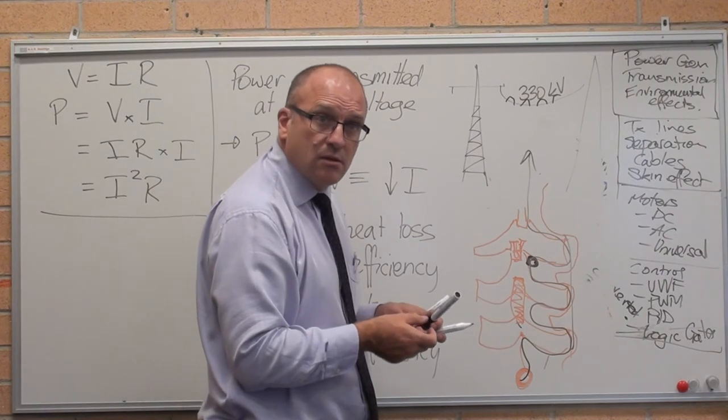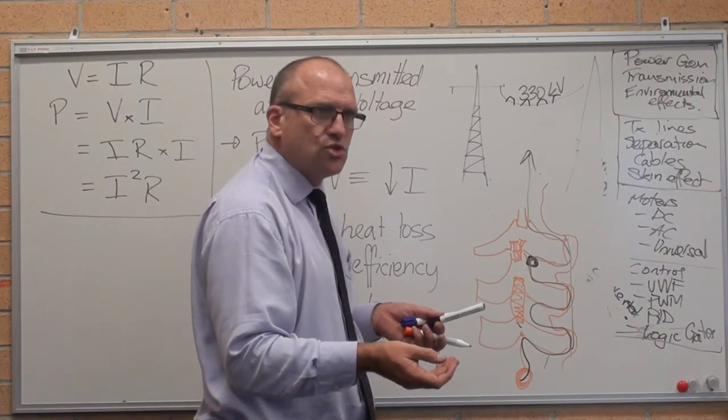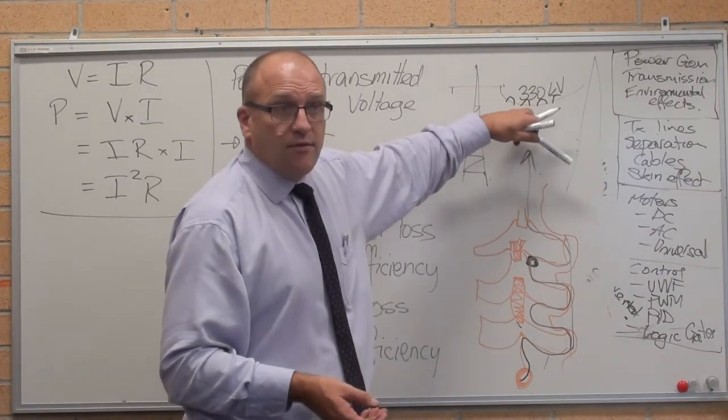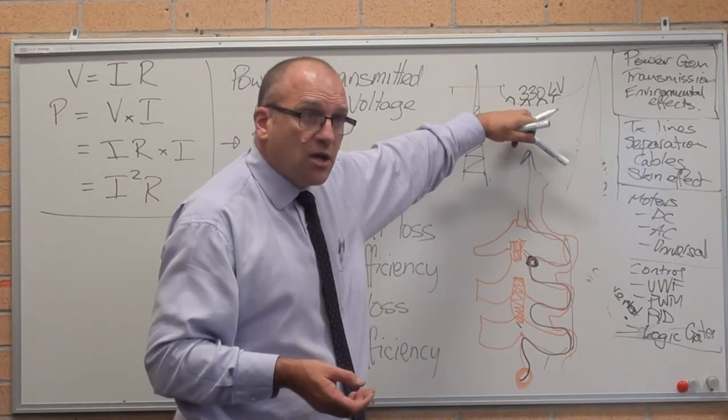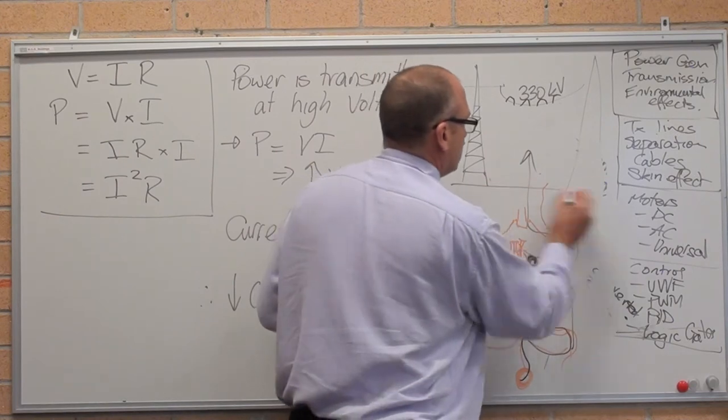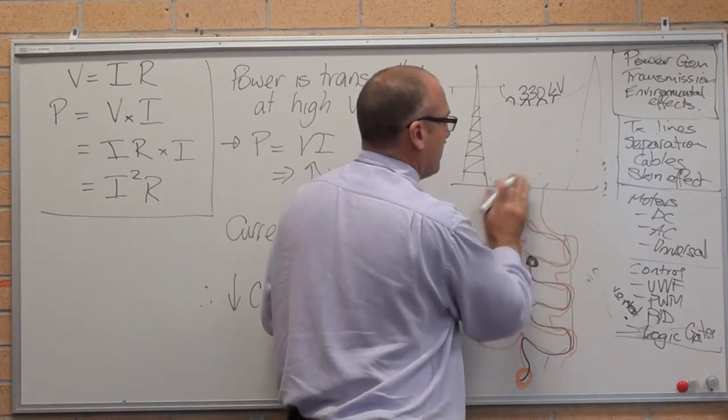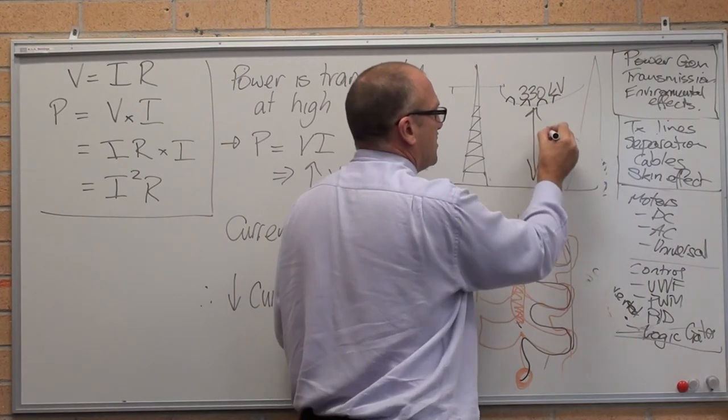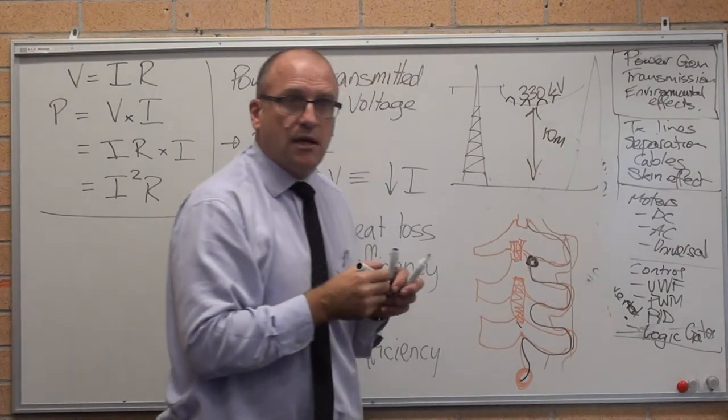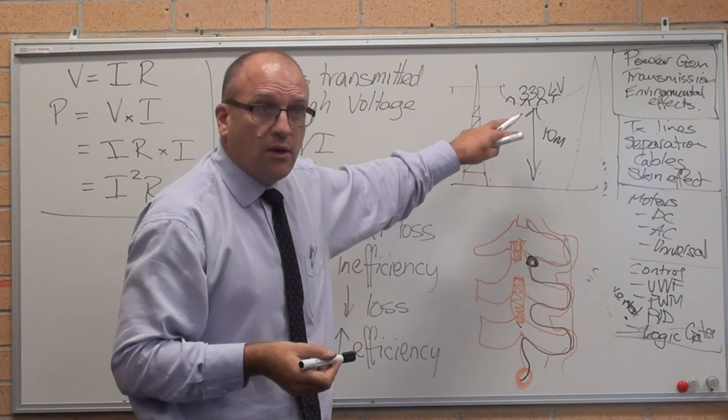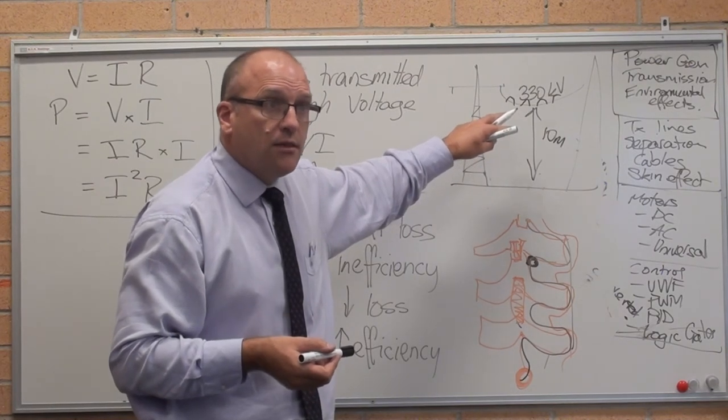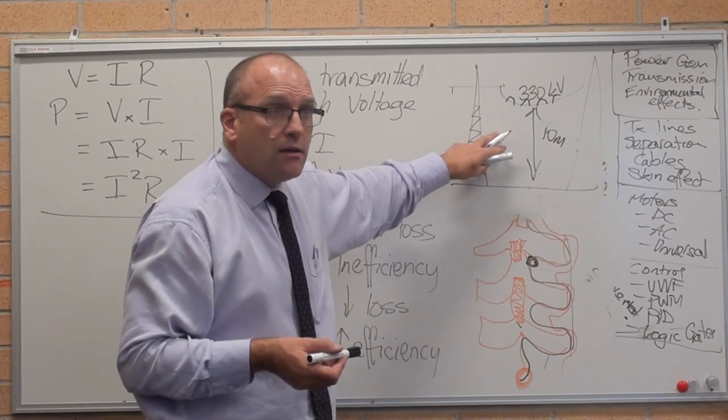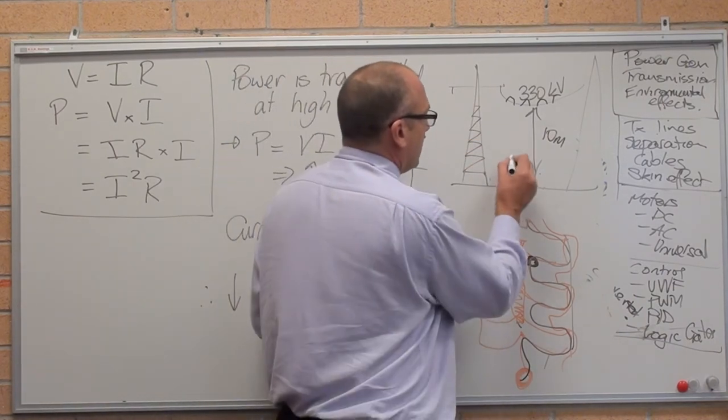So once again, minimizes shorting out. So 330 kV. Those power lines are incredibly high as well because voltage is the driving force. 330,000 volts will drive a spark happily 10 meters. You can't build underneath a high voltage power line. You can't drive trucks underneath them unless they're designed accordingly.